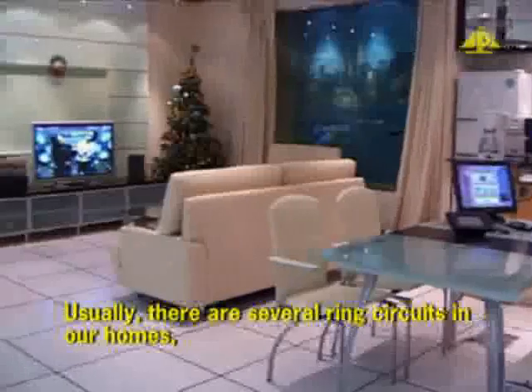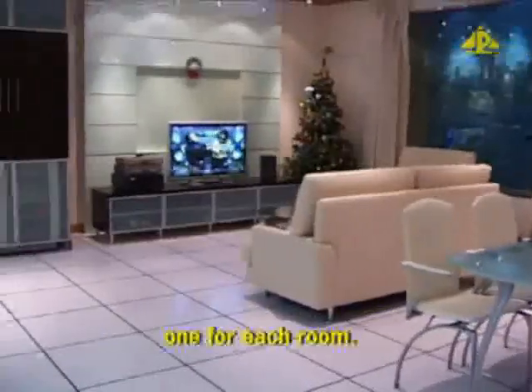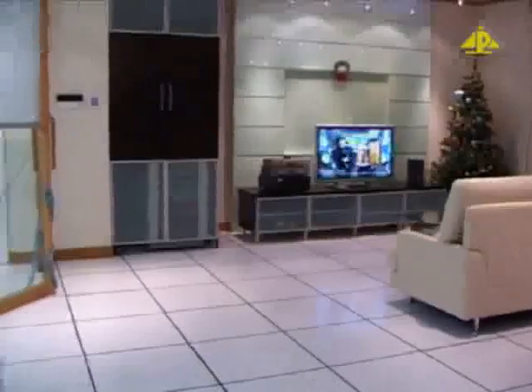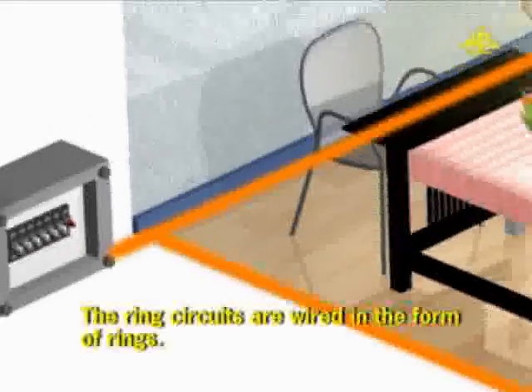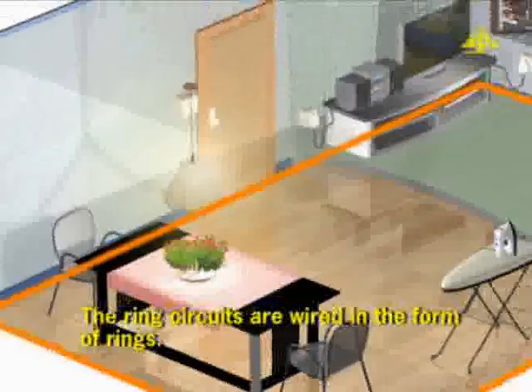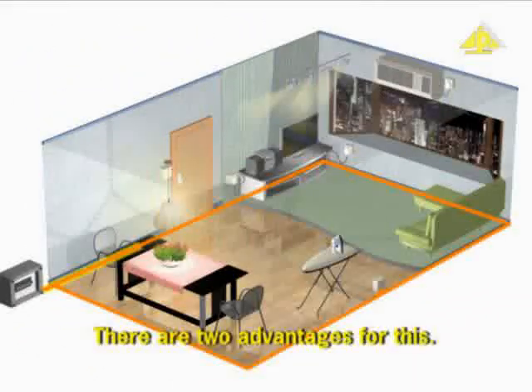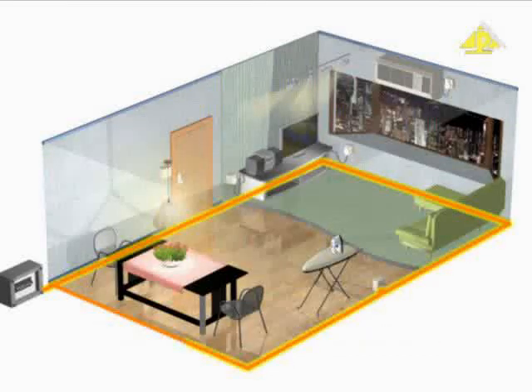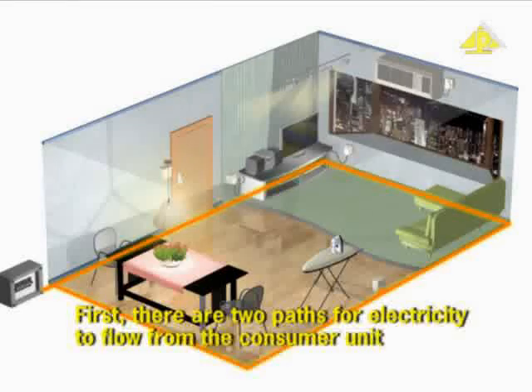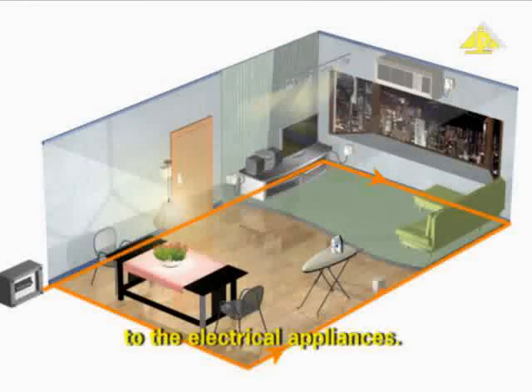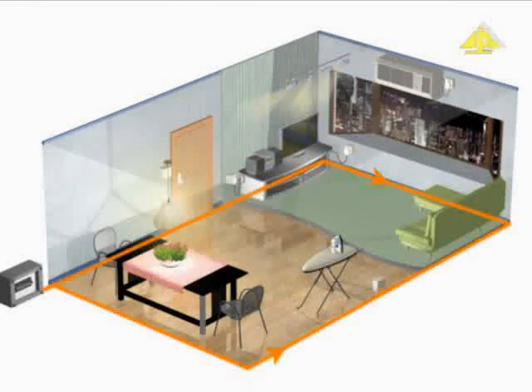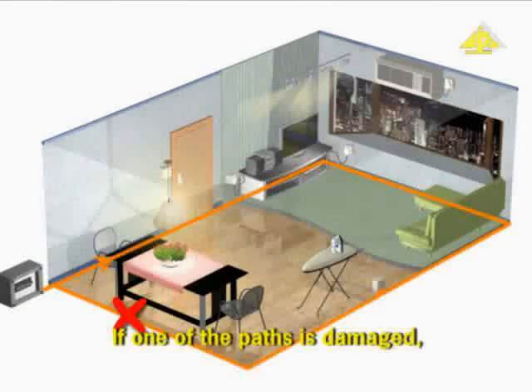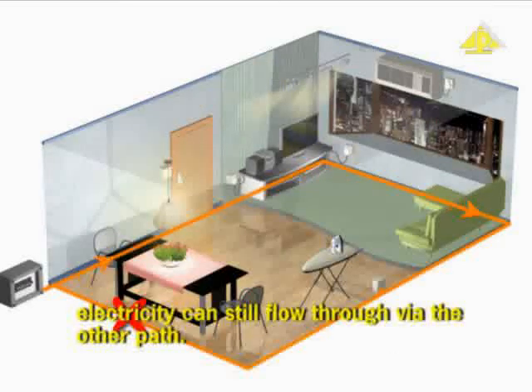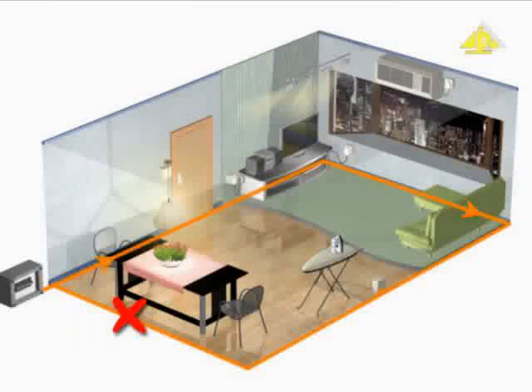Usually, there are several ring circuits in our homes, one for each room. The ring circuits are wired in the form of rings. There are two advantages for this. First, there are two paths for electricity to flow from the consumer unit to the electrical appliances. If one of the paths is damaged, electricity can still flow through via the other path.